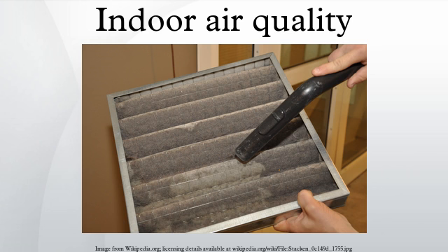Molds and other allergens. Main articles: mold health issues, mold growth, assessment, and remediation. These biological chemicals can arise from a host of means, but there are two common classes: moisture-induced growth of mold colonies and natural substances released into the air such as animal dander and plant pollen. Mold is always associated with moisture, and its growth can be inhibited by keeping humidity levels below 50%. Moisture buildup inside buildings may arise from water penetrating compromised areas of the building envelope or skin, from plumbing leaks, from condensation due to improper ventilation, or from ground moisture penetrating a building part.